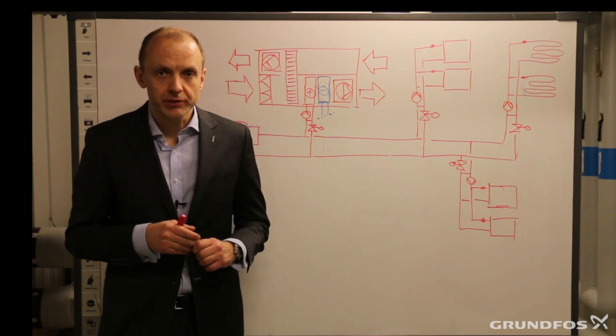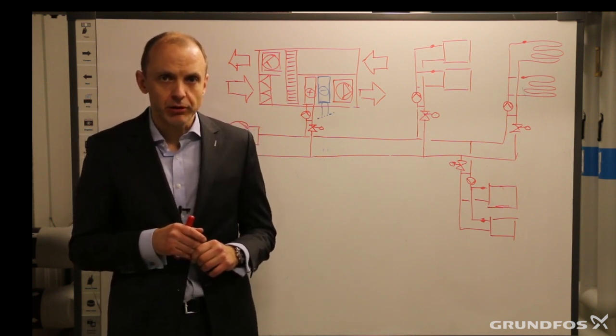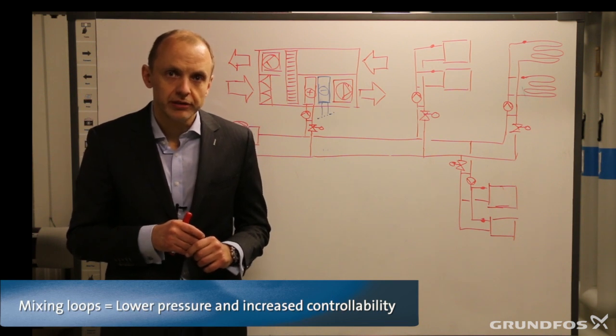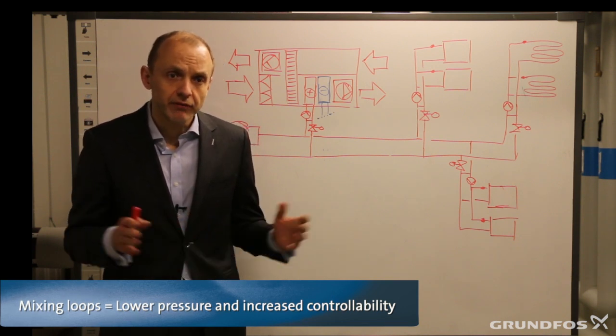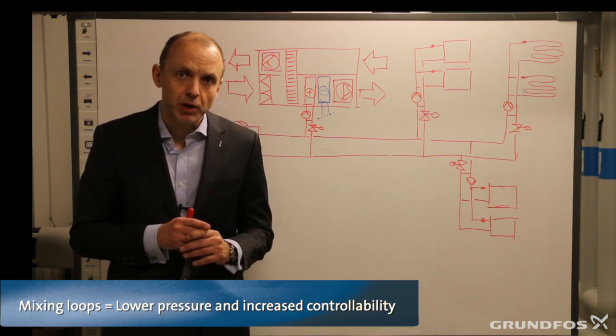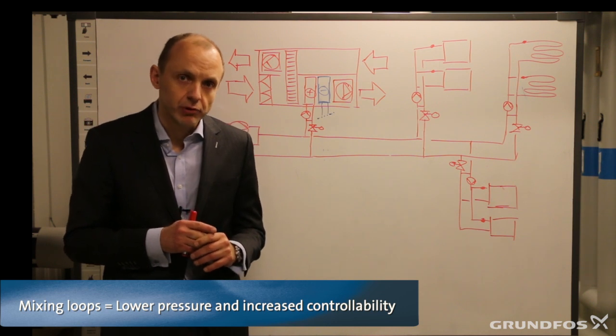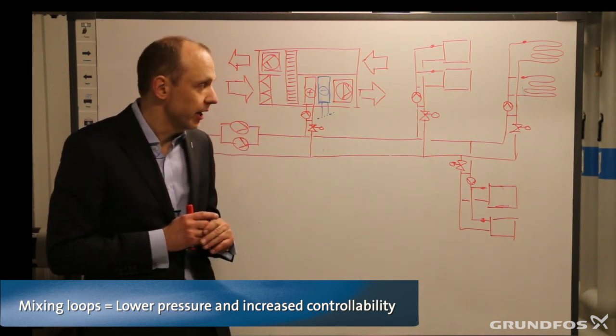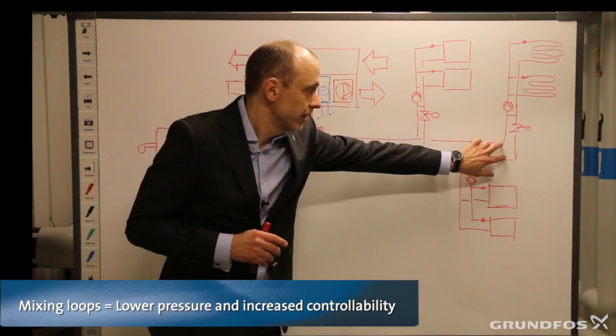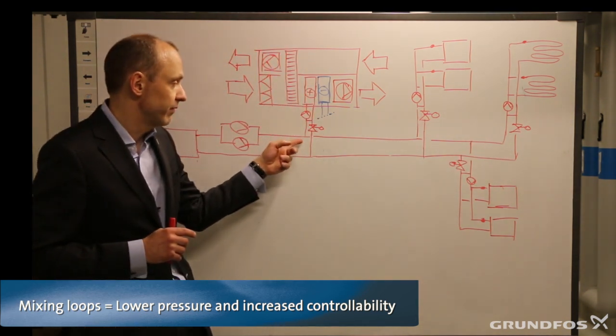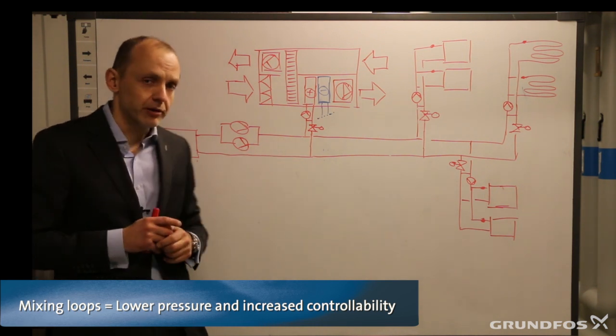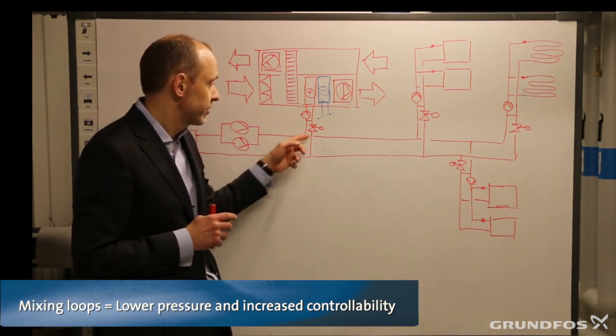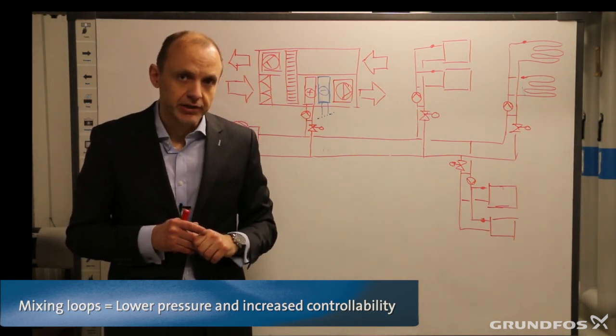By introducing mixing loops in this system, we are able to reduce the main pump size and also the pressure provided by the main pumps. That means we are able to reduce the differential pressure in the system as well. One of the typical problems with HVAC systems is too high differential pressure close to the pumps, because pumps are designed to maintain constant differential pressure at the furthest point. By using smaller pumps providing less pressure, we reduce the delta P close to the pumps, which gives better controllability of the system.